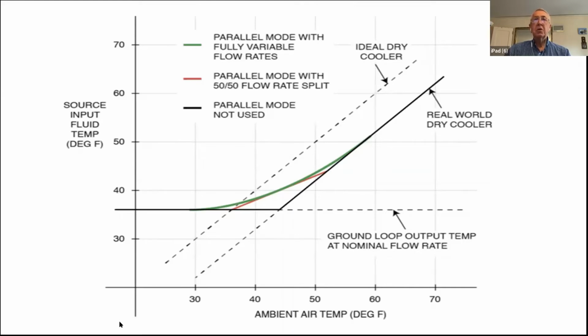We'd have an extremely low efficiency for the heat pump if we had to depend on only this line right here. No good. So basically, instead of that, if we have a ground loop, we can operate up here. So what we're saying is when the temperature is very low for the outdoor air, we have a ground loop which feeds, in this case, is not very warm. What we're showing is about a 36-degree Fahrenheit temperature for the water that can come into the heat pump. That's still reasonably good efficiency compared to way down here of zero or something.